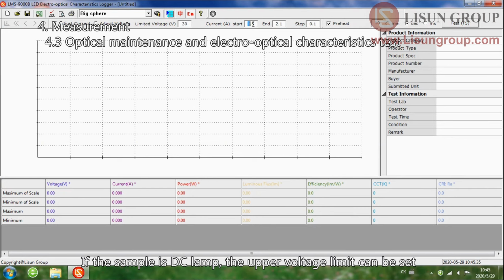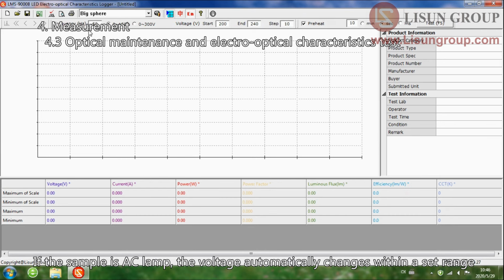If the sample is a DC lamp, the upper voltage limit can be set and the current automatically changes within a range, or the upper current limit can be set and the voltage automatically changes within a range. If the sample is an AC lamp, the voltage automatically changes within a set range. During the test, the horizontal axis of the software displays different voltage or current values that change automatically, and the vertical axis shows the curves of other parameters.